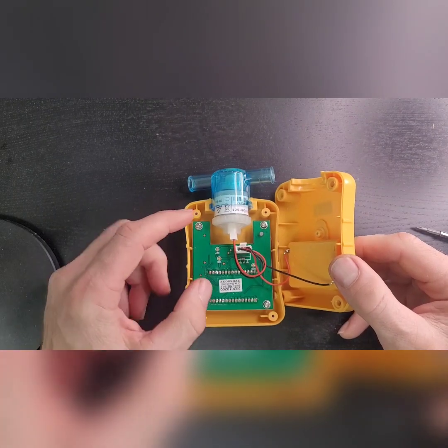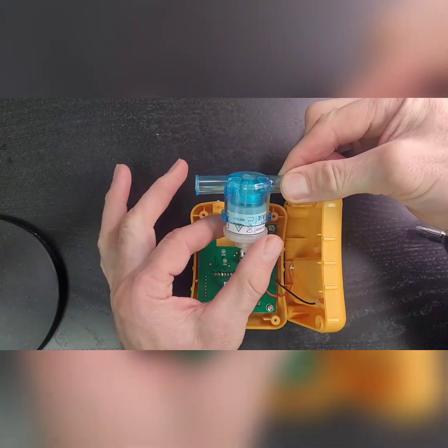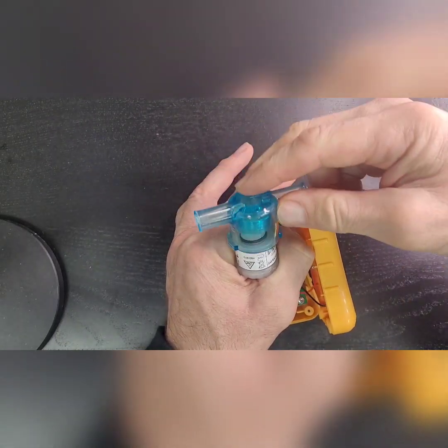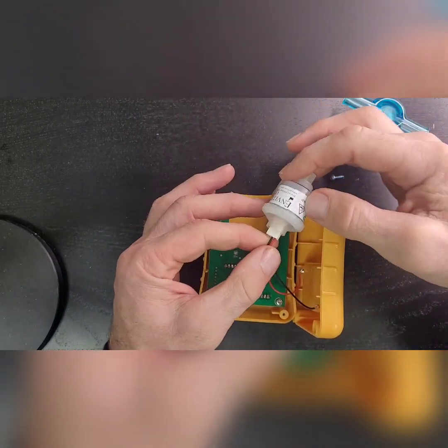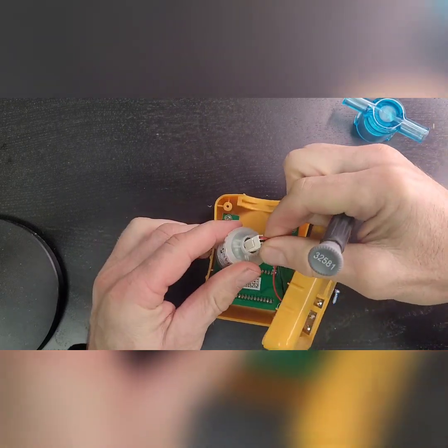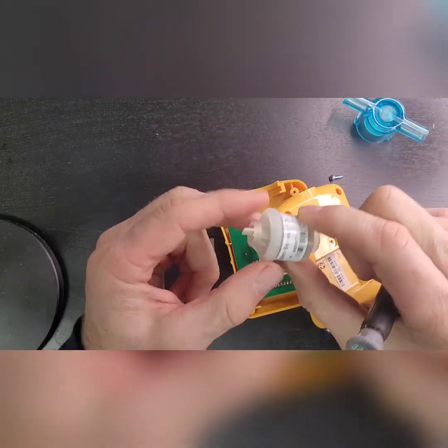What you'll see right over here is the sensor, which has a standard universal connector jack. Go ahead and pop that off — it's quite simple. The sensor has a thread, and it's made for this exact purpose — for the manifold to screw on. Take that off and there's a little clip over here. Just draw that down and take it out — pop it down and it comes out. That is the sensor that will be discarded; you throw that away.